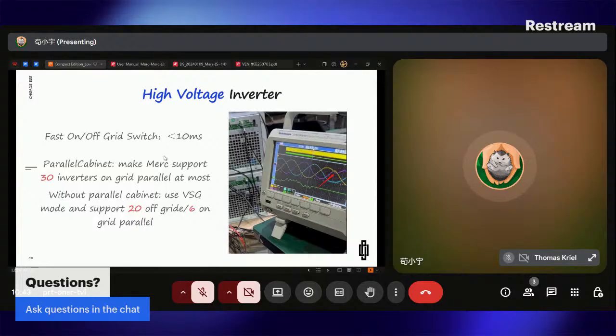Sometimes when we talk about the switch time, we know it's very fast, but we don't understand how fast it is. If you are using a desktop computer, Intel requires the power supply manufacturers to keep the 12 volt output, when there is a power outage, for longer than 17 milliseconds. So our switch time is lower than that, which means if you are using a desktop computer, when the grid is down, your computer will still have power. It will not shut down or restart. So you don't need to connect a UPS or something.